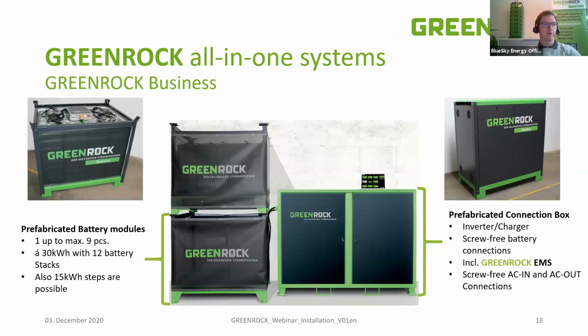Now we finally get to the GreenRock Business System. You see we don't use the stack size here anymore, we use a whole pallet with 12 of each stack already placed on one. You can also scale them or place them above each other. For example, this would mean 60 kilowatt hours in capacity and 12 kilowatt on power. In this case, we do not place the power box on top, we place it in an additional case right next to the modules. Inside there we again have a battery inverter, some easy screw-free connections for the battery, a GreenRock EMS again placed inside, and really easy to install AC in and AC out connections.